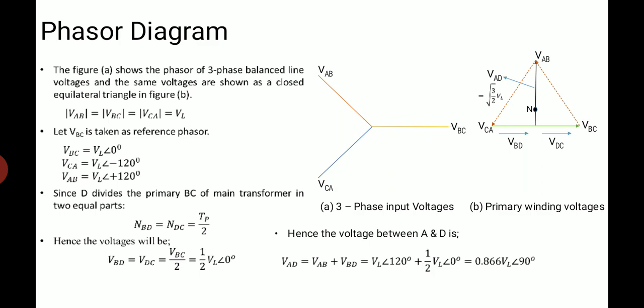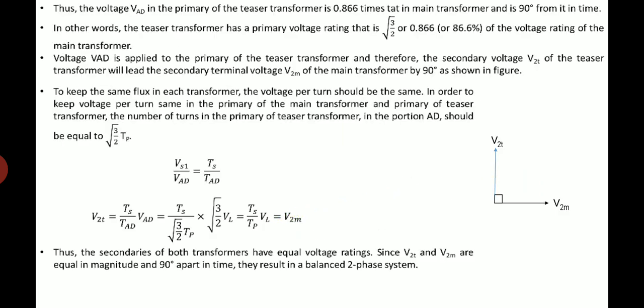As the D point divides primary BC of main transformer in two equal parts, the voltage between A and D is VAD is equal to VAB plus VBD is equal to 86.6 percent of VL angle 90 degree. Thus the voltage VAD in the primary of teaser transformer is 86.6 percent times that in main transformer and is 90 degree from it in time.